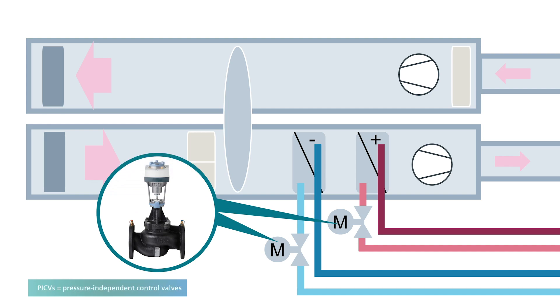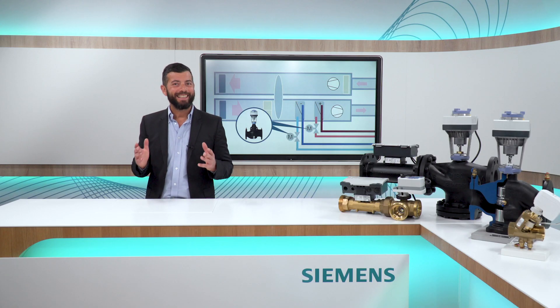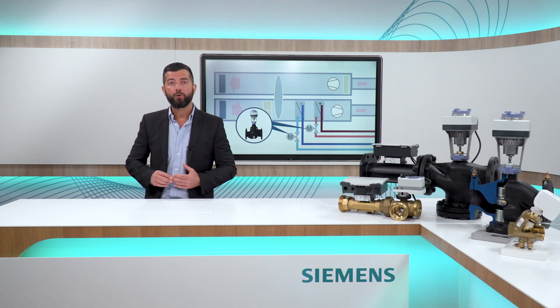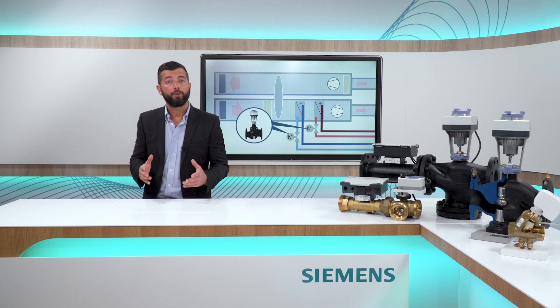For AHU applications, there are two dynamic balancing solutions I would like to recommend. The first one is to use a standard PICV with an electromotoric actuator, and make sure that the air temperature control is fine-tuned. With the standard mechanical PSEV, you can guarantee that the flow circulating through the heating and cooling coils is exactly what the AHU requires to heat up or cool down the air or to reduce humidity.